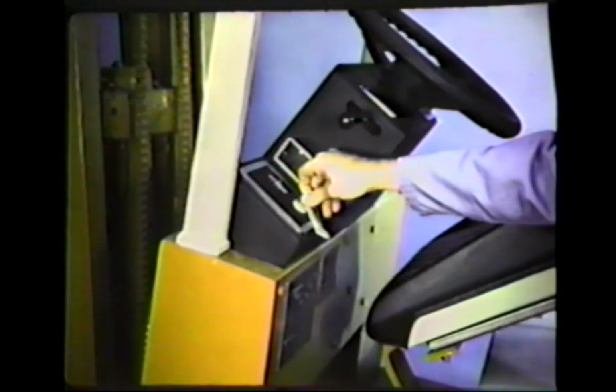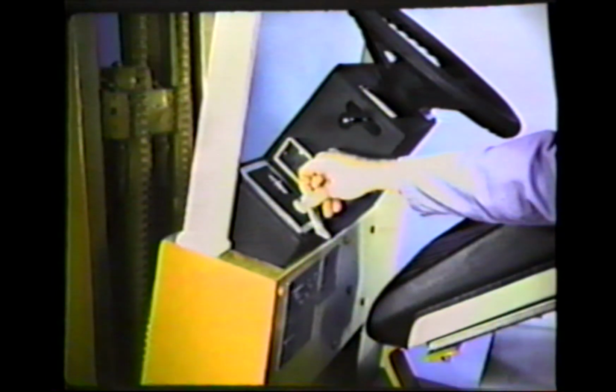The PMT function can be reset by returning all switches to the off position. If the contactors double trip after the PMT is reset and the switches are reactivated, the problem is definitely in the turn-off circuit.